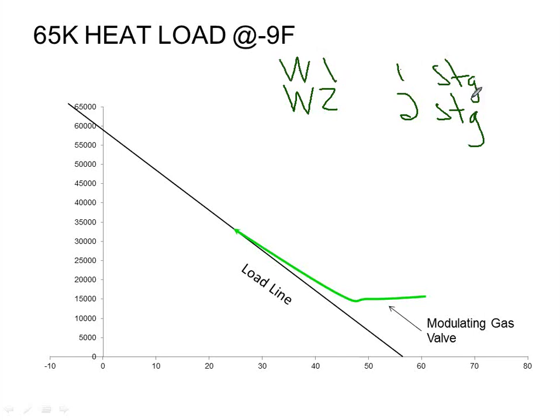Joel asks, how well integrated are the new Infinity units with modulating gas valves with Carrier Comfort Zone systems? You would not be using this furnace with a Carrier Comfort Zone system, because a Comfort Zone system is doing what I was just describing here with the 1-stage, 2-stage. Comfort Zone is basically just a big thermostat with a zone panel, not much different than a Honeywell zoning system.